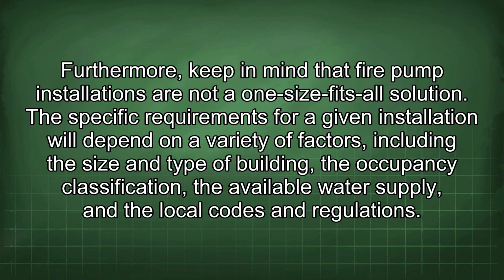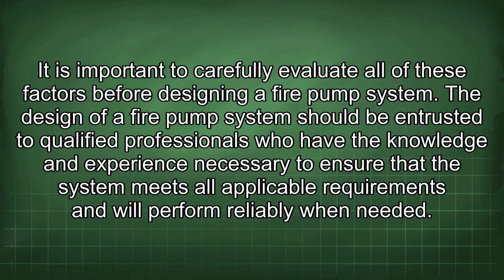Furthermore, keep in mind that fire pump installations are not a one-size-fits-all solution. The specific requirements for a given installation will depend on a variety of factors, including the size and type of building, the occupancy classification, the available water supply, and the local codes and regulations. It is important to carefully evaluate all of these factors before designing a fire pump system. The design of a fire pump system should be entrusted to qualified professionals who have the knowledge and experience necessary to ensure that the system meets all applicable requirements and will perform reliably when needed.